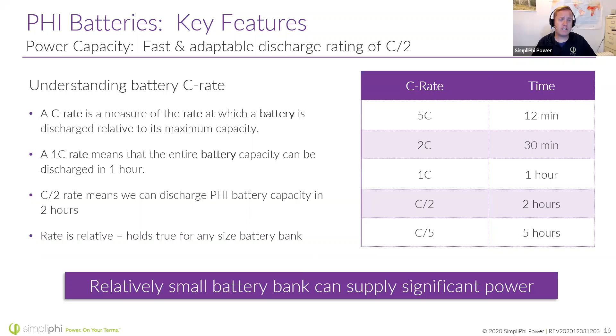So if you got a short solar window and you want to charge that battery up quickly, we can push a lot of power into the battery, get it charged up before the sun goes behind that tree, goes behind that shade structure. If we want to run a generator, we can run that generator at full tilt, charge those batteries up, shut that generator down, let the generator not accumulate as much runtime, save fuel. Lead acid batteries are looking at C/20, C/5. If you're really pushing a lead acid battery, more like C/10 is what you're going to see in a lead acid battery bank.